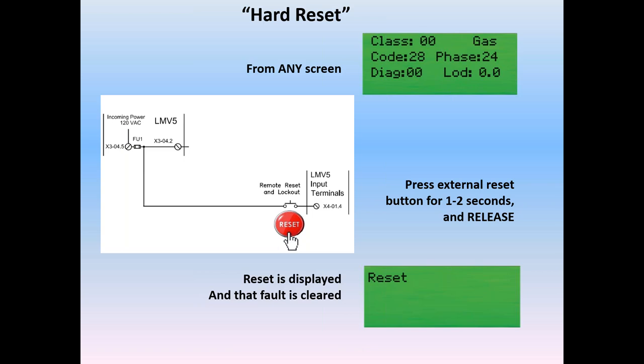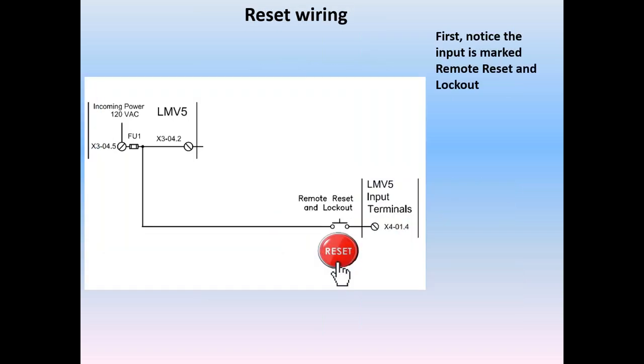Let's take a closer look at that reset circuit. Reset wiring: notice that the input is marked remote reset and lockout, because that's exactly what the function of that input is. If you are in a lockout and you push this button, you take line voltage and you present it to X4-01.4, and this causes the LMV to do a reset. However, once the fault is removed, if you apply power to this terminal again, you will in fact cause a manual lockout. This has caused a lot of confusion with customers.